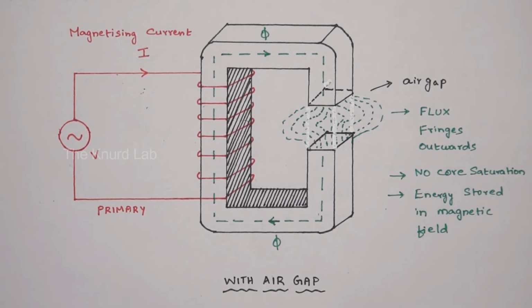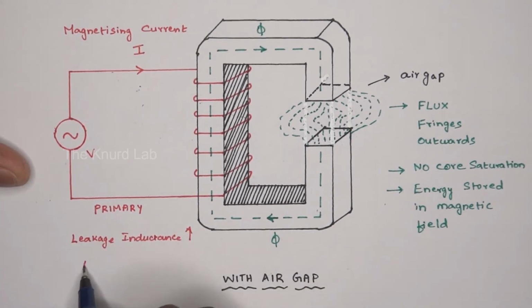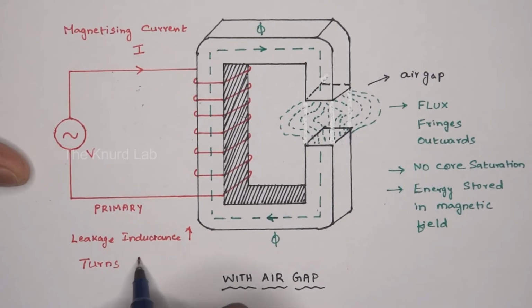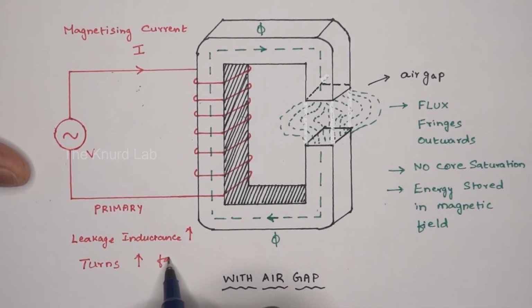This is exactly what enables storage of energy in the form of magnetic field in the air gap. Due to this, the leakage inductance increases, and you would have to increase the number of turns to maintain the same amount of inductance value. This stored energy is what causes the flyback, or the high voltage across the coils, during changes in the input current.